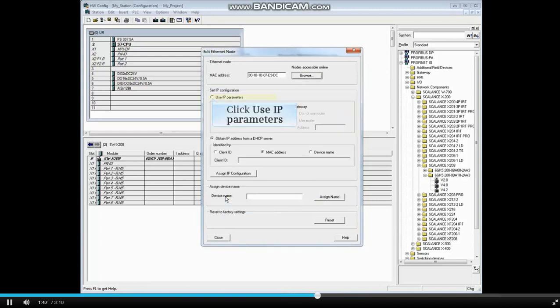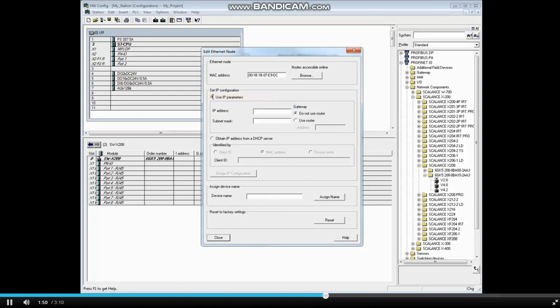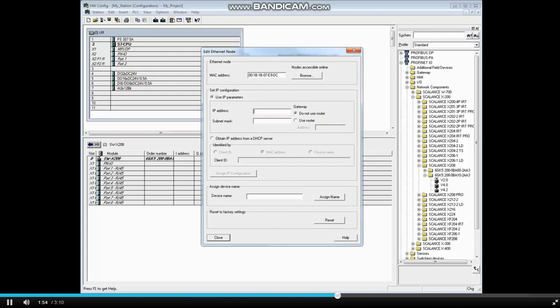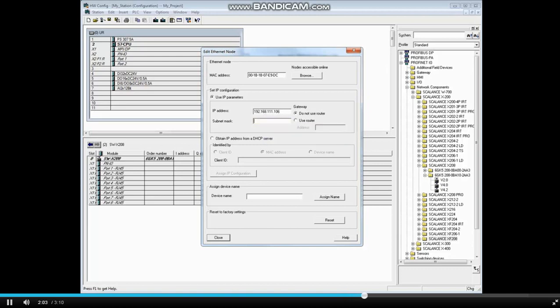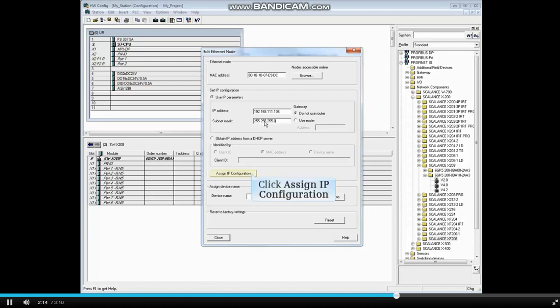Click the radio button, use IP parameters. Select the IP address box and type the address 192.168.111.106. Select the subnet mask box. This network is a class C network and we will add the subnet mask 255.255.255.0. Now click the Assign IP configuration button.